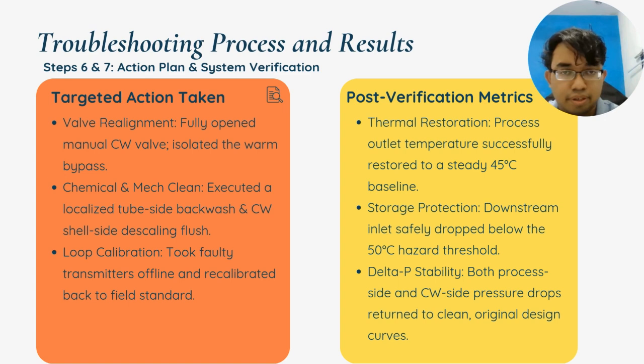And then post-verification metrics is that thermal restoration. The process outlet temperature successfully restored at the steady 45 baseline. The storage protection downstream inlet safely dropped below the 50 degree hazard threshold. And Delta-P stability, both pressure drops across CW return to clean and original design.